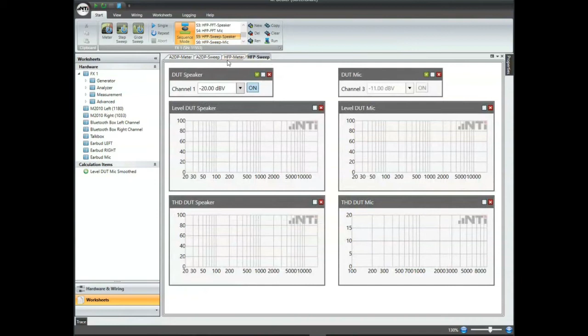The HFP profile, as you remember, is bidirectional but mono, so a single channel profile, which means of course one channel only. So I can only test the speaker first, and then in a second step, the microphone. Maybe you heard in the background the test tone from the TalkBox. So here, this is the spectrum of the loudspeaker of my earbud, and this is the microphone of the earbud and the corresponding distortion values. The next step would be, as before, the frequency response measured with a glide sweep. Here we have it from the speaker, and the last step would be the microphone. That's what you see here. Here we have the frequency response from the microphone and the distortion response.